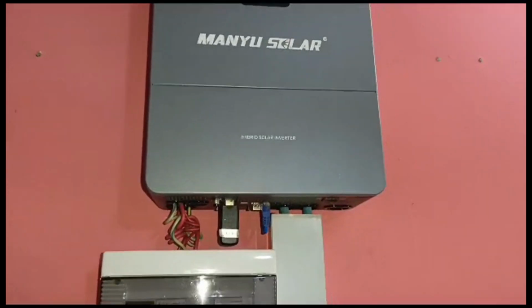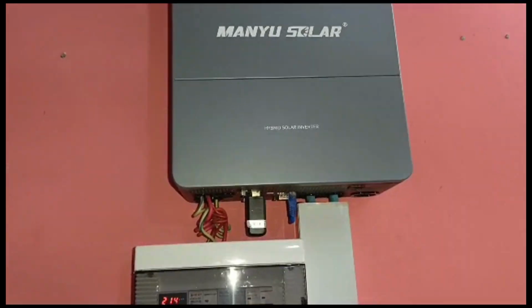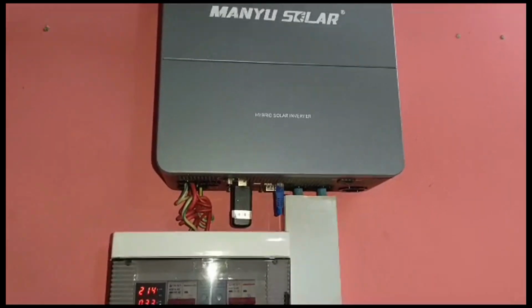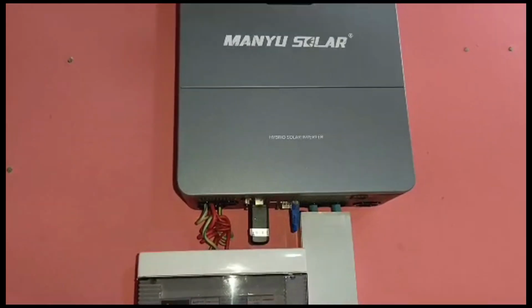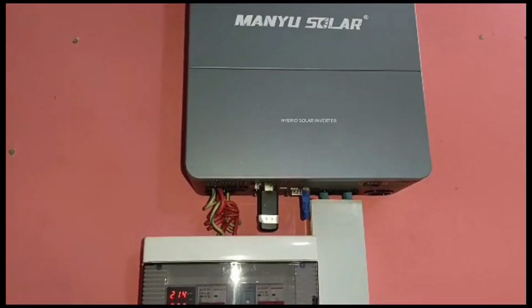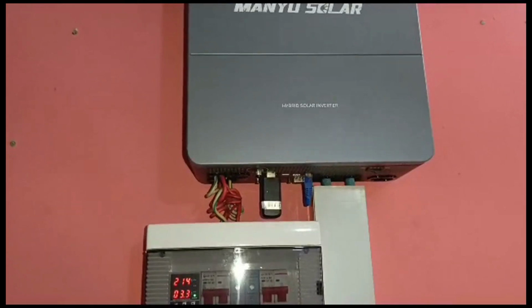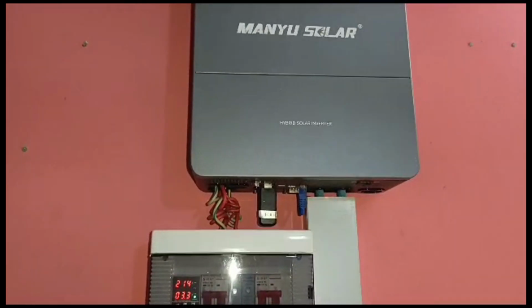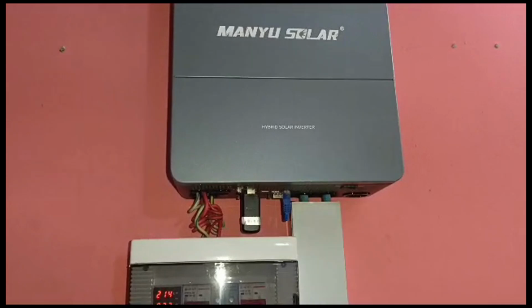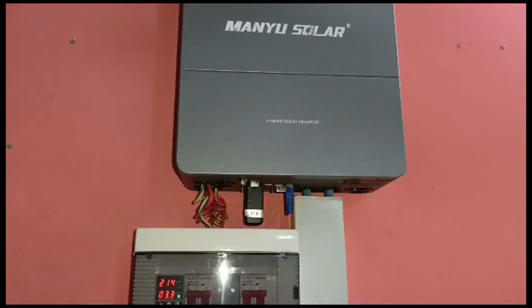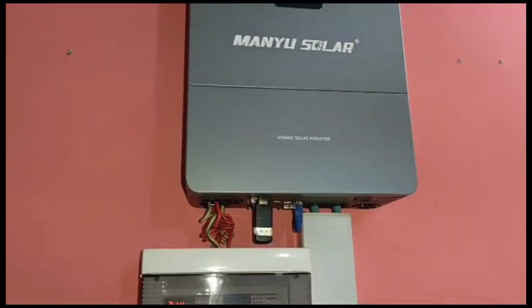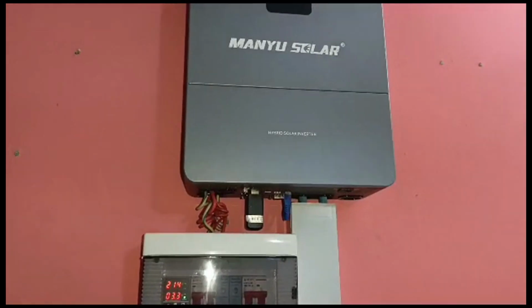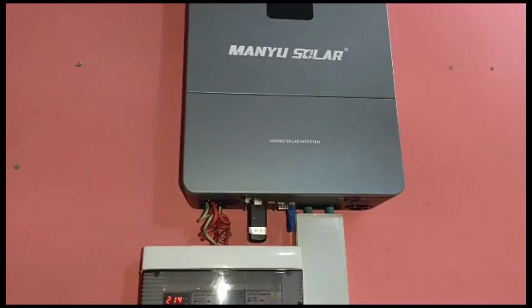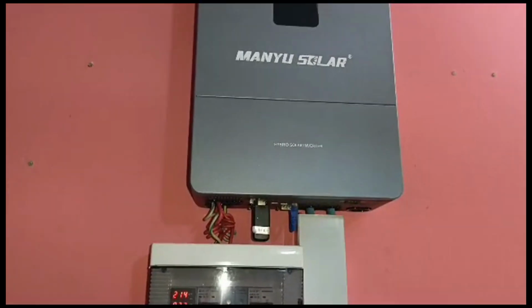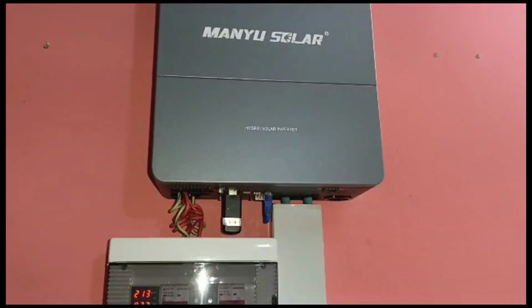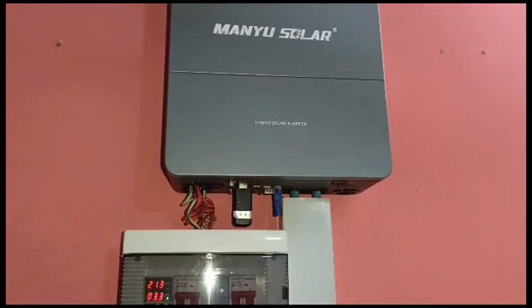So because of that, I made the decision of putting two sets of sockets by the freezer and the fridge. One is directly connected to the grid and the other is connected to the inverter. By default it is always connected to the socket that goes directly to the grid. In case of a prolonged power outage of 24-48 hours, then we start looking at putting it on the inverter. So the main loads on the inverter are the lightings and the fans.